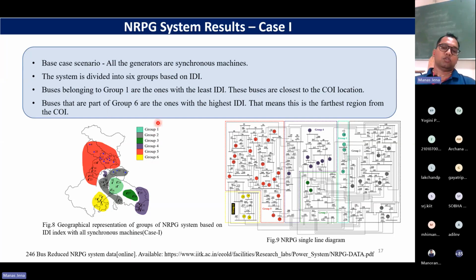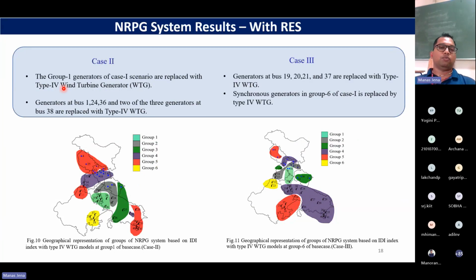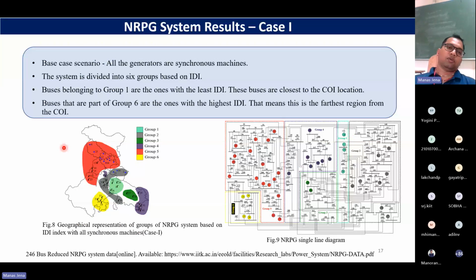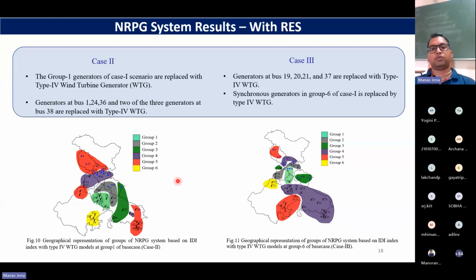For the base case, we got these groupings, and then we replaced some of the machines with inverter based resources. And then we again found the grouping for case 2. Again we had a case 3, where a few more generators of a particular group of the base case were replaced with inverter based resources. Essentially the logic is, you first find out the inertia distribution for the base case. Then let us say you start integrating inverters, either you replace a few generators or you add inverters, whatever it is, and then recalculate the distribution and see how the groups are getting impacted.